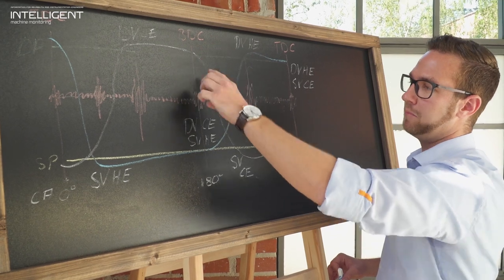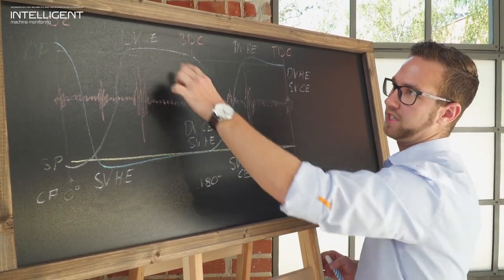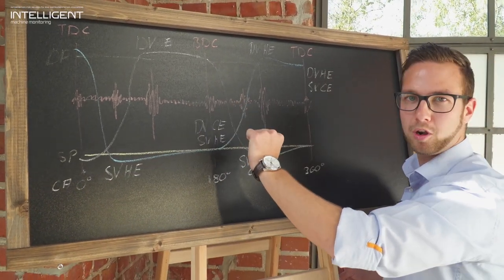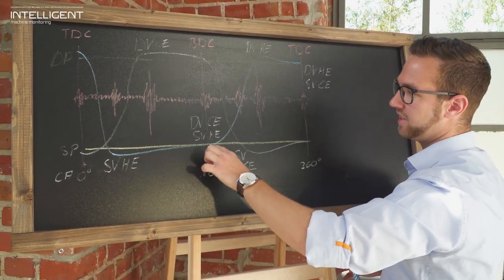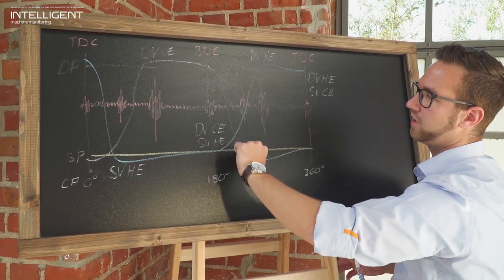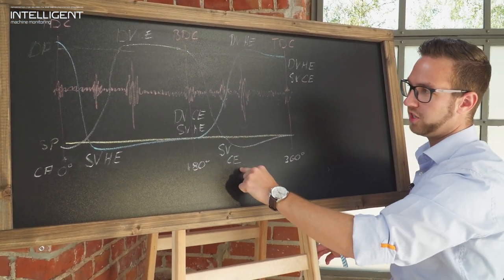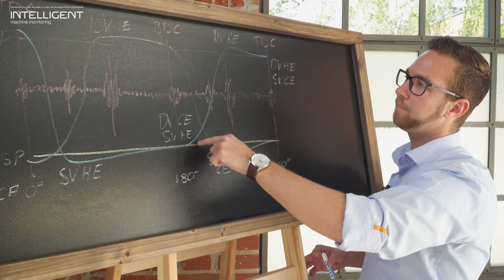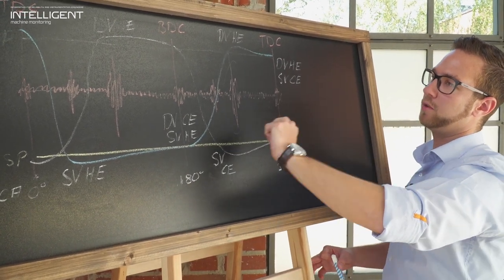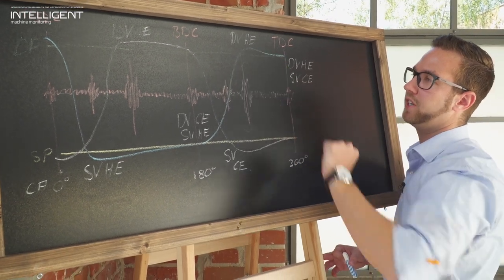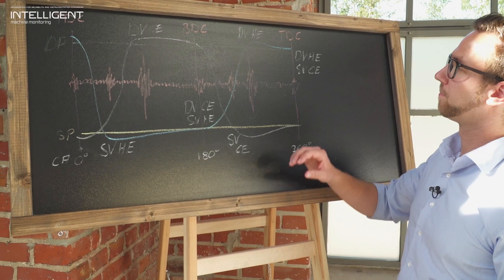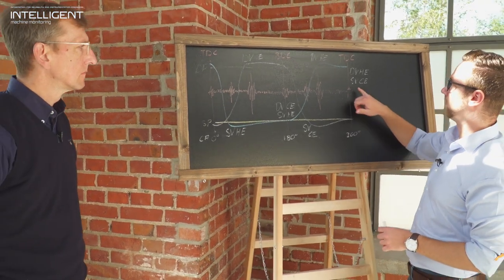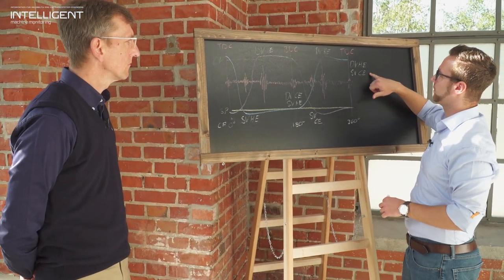Then when we come to the bottom dead center (BDC), the discharge valve crank end which has opened here, and the suction valve head end which has opened here, are closing again, which is usually a smaller peak. If we go further, on the crank end side the pressure is decreasing. We drop below suction pressure level and the suction valve crank end side will open. At the same time, the pressure at the head end side will rise above the discharge pressure level and the discharge valve on the head end side is opening, creating this high peak. The whole thing is repeated for every revolution. On the top dead center, there's the last two valves closing again. All in all, there are eight actions that we can see in this vibration curve.